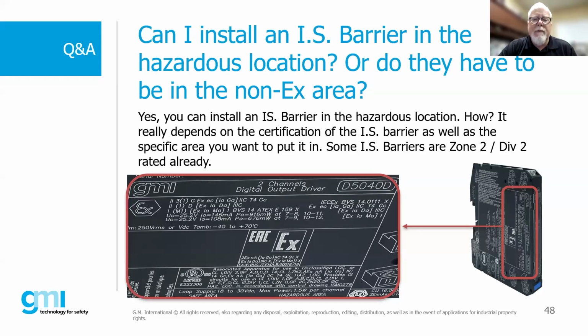And then it'll say for use in a Class 1 Div 1 area for circuits. So what that's telling us is that we can install barriers, depending on the brand and the model. Most barriers from most brands are like this - they'll allow you to install them in a Division 2 or Zone 2 area.